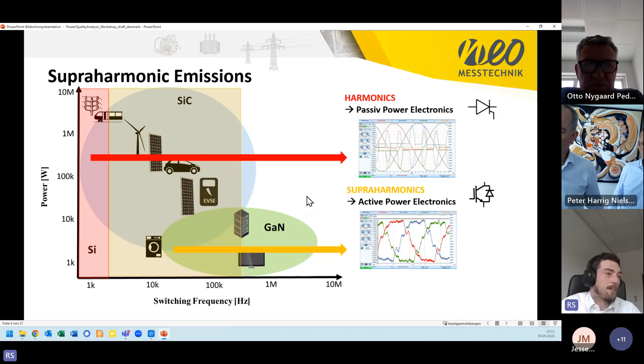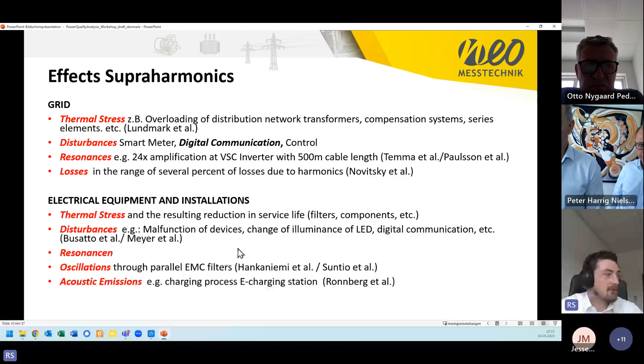This is quite different if we compare the grid and the electric equipment and installations. Regarding the grid, we have thermal stress. For higher frequency currents in capacitors, the current consumption gets higher, and therefore compensation stations get under thermal stress and get damaged, reducing their lifetime. There were studies done about this, and we see this is also an effect that causes problems.